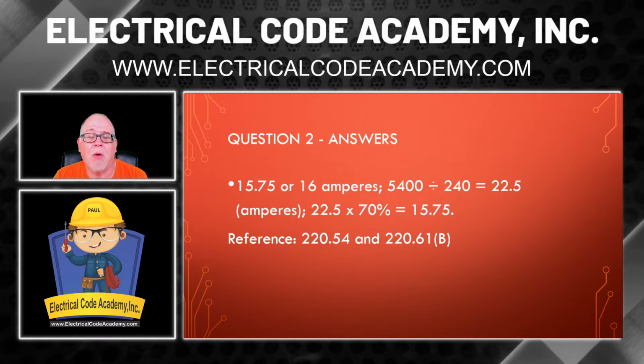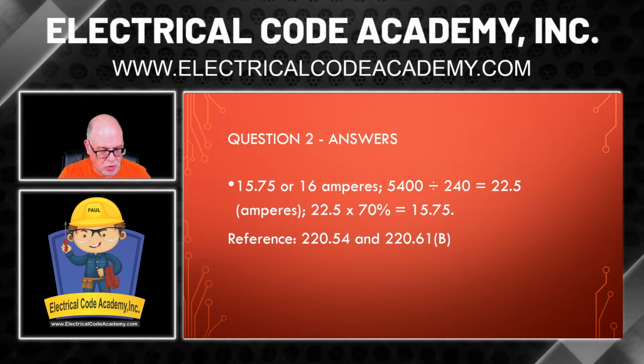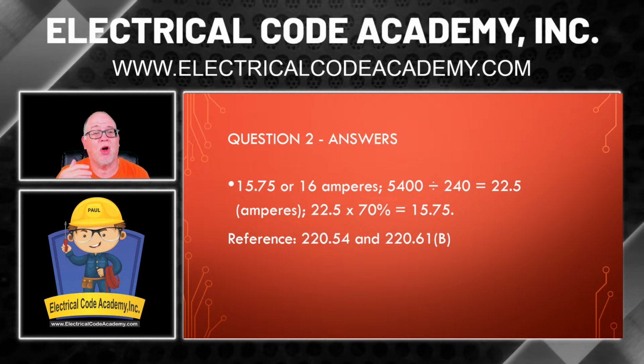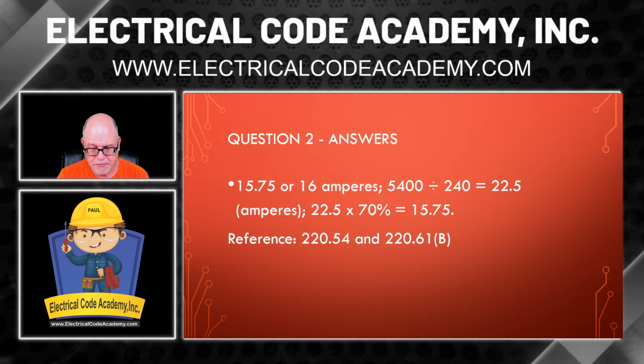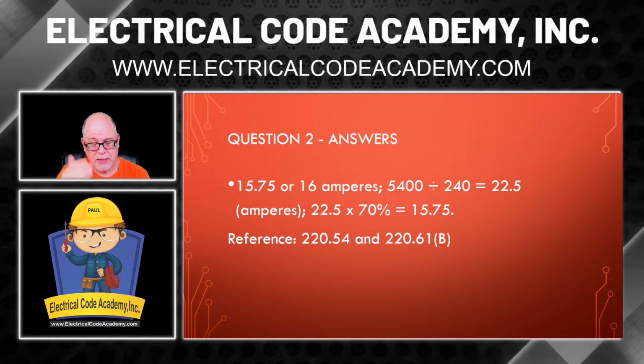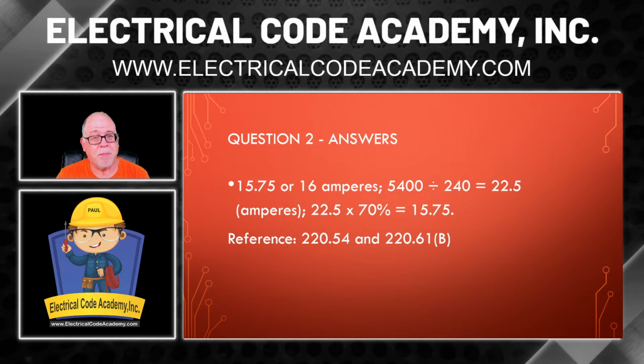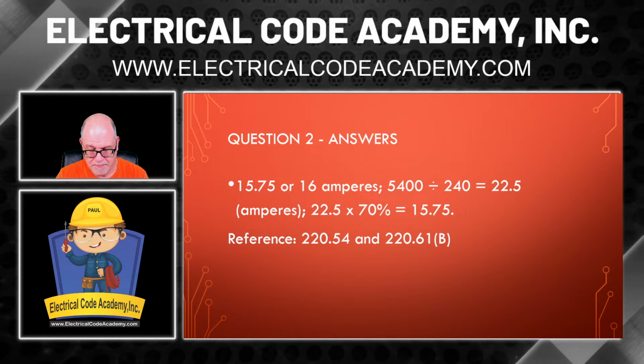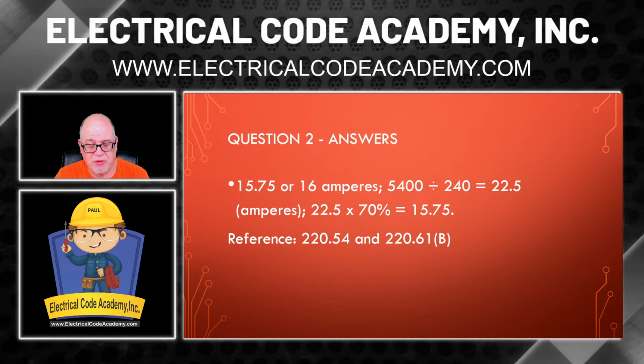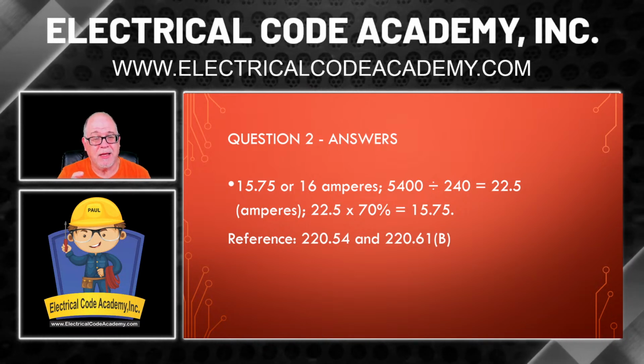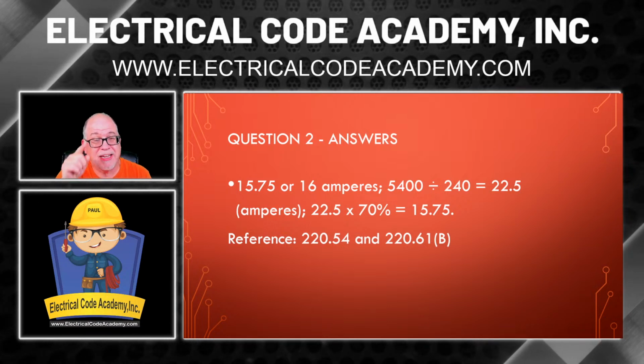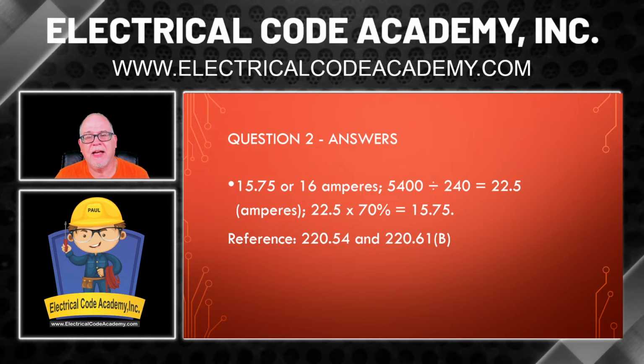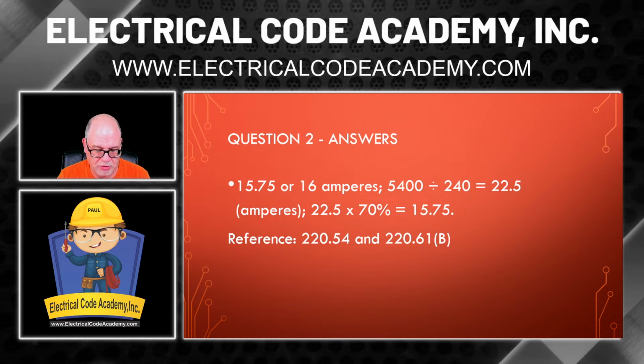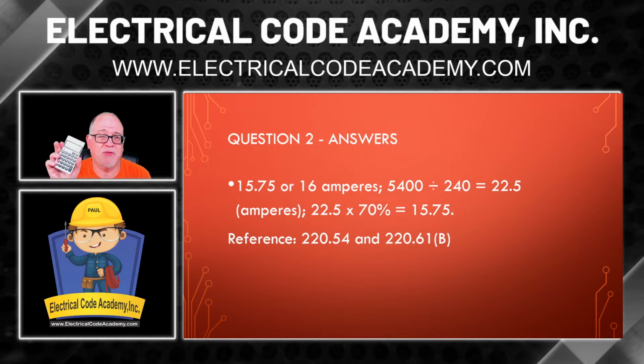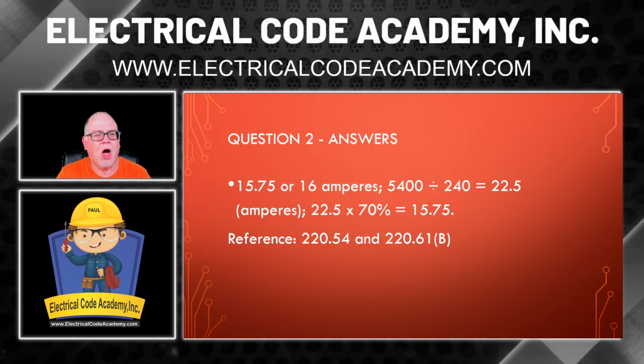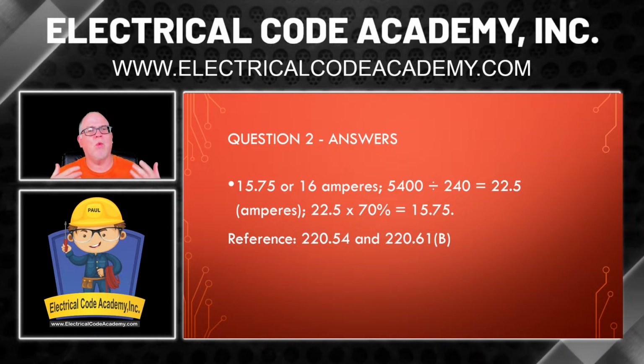Now, I want to talk about the other way you could have done this. One other way you could have done this is start with our full value, our 5,400, and you could have multiplied that by 70%. And that gives you 3,780 VA. Then you could take that and divide that by 240 volts. And that also gives you 15.75. Always remember, there are many ways that you can do this.